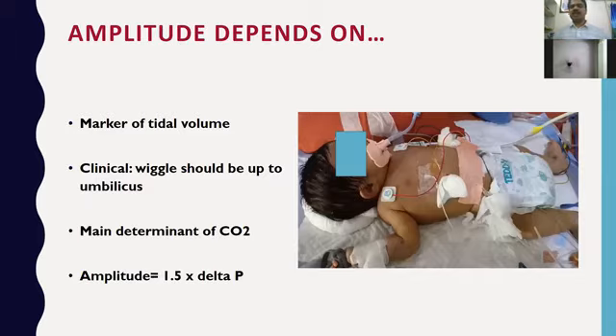If it extends to the lower abdomen or thigh, it means the amplitude you are giving is more, and you need to come down on that. This is one of the main determinants of CO2 removal, as we discussed. As a rule of thumb, you can set the amplitude at 1.5 times delta P.